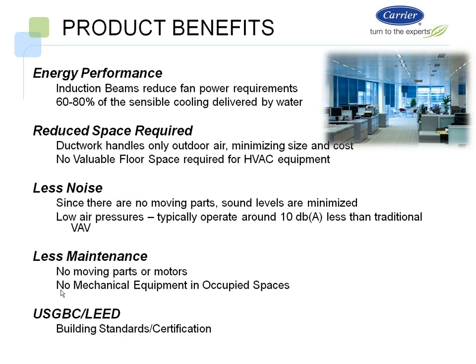Again, from the energy performance standpoint, typical induction beams reduce fan power requirements, with 60 to 80% of the sensible load now being delivered by cool water. Rather than trying to transfer air all across the building, water is still the best medium for heat transfer. It's been around forever. And again, reduced space required. The ductwork space is now smaller because you're using less ductwork and moving less air through that ductwork.